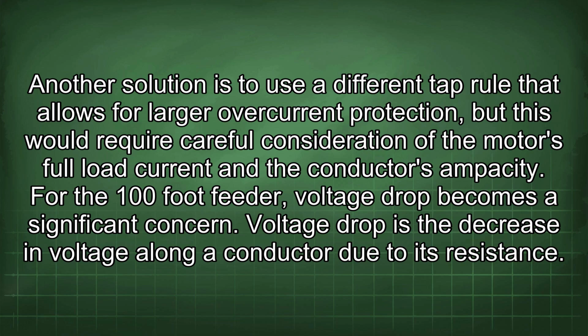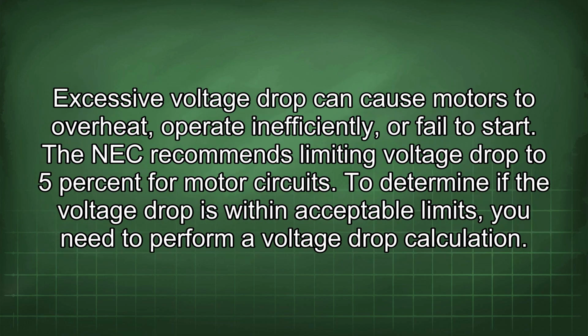For the 100-foot feeder, voltage drop becomes a significant concern. Voltage drop is the decrease in voltage along a conductor due to its resistance. Excessive voltage drop can cause motors to overheat, operate inefficiently, or fail to start. The NEC recommends limiting voltage drop to 5% for motor circuits.